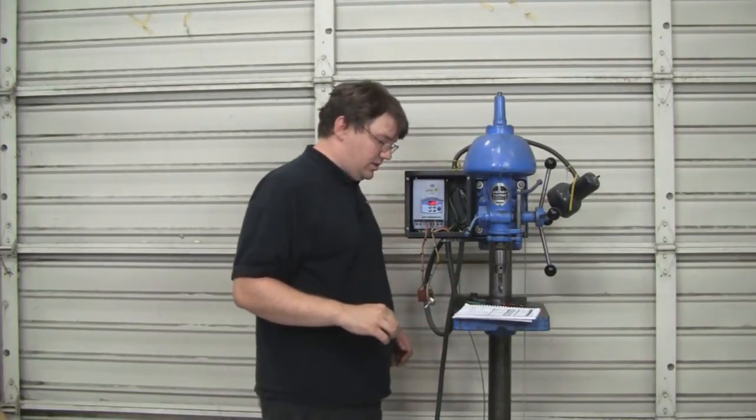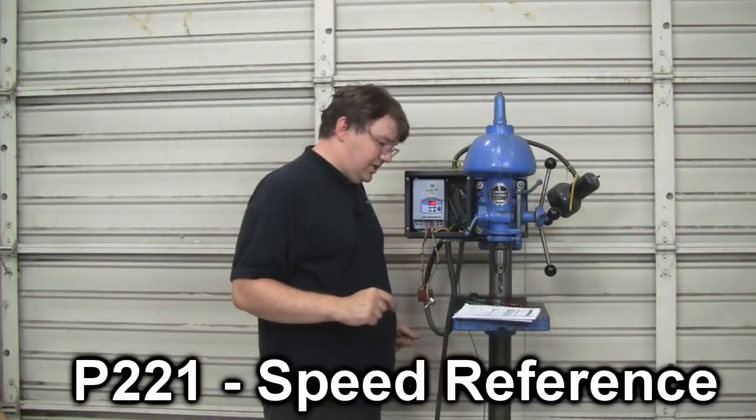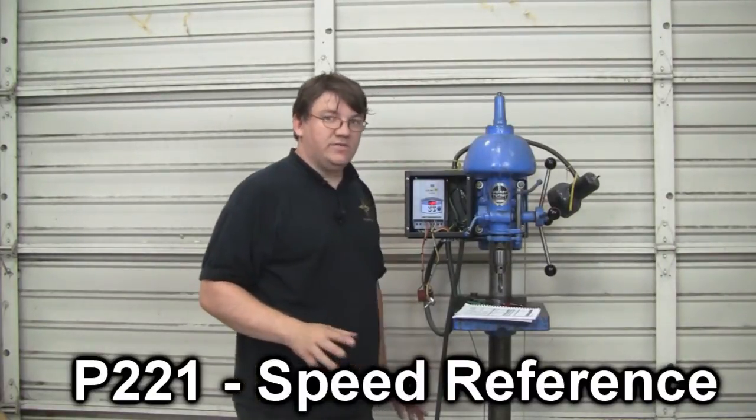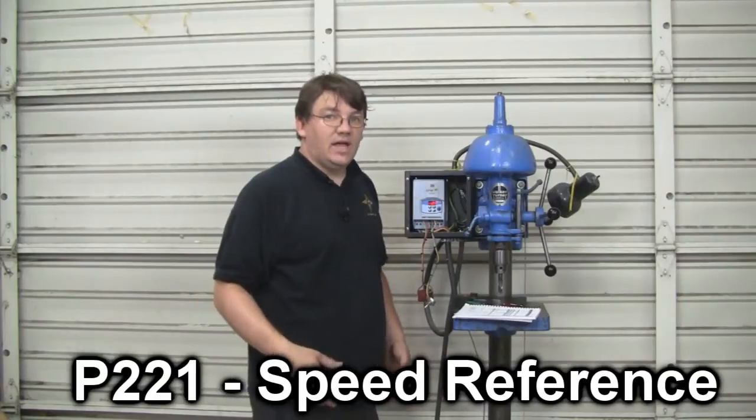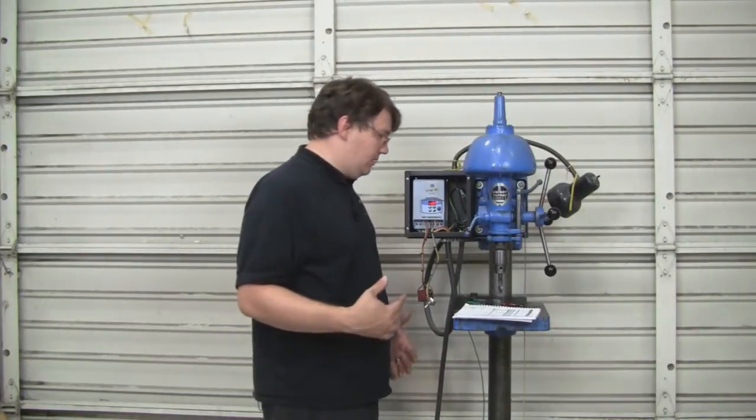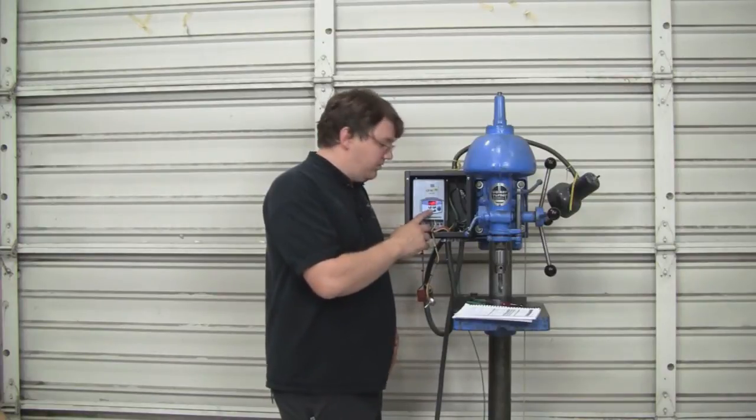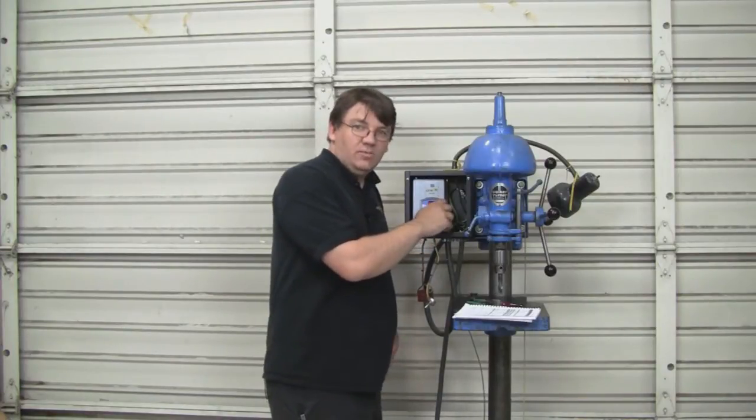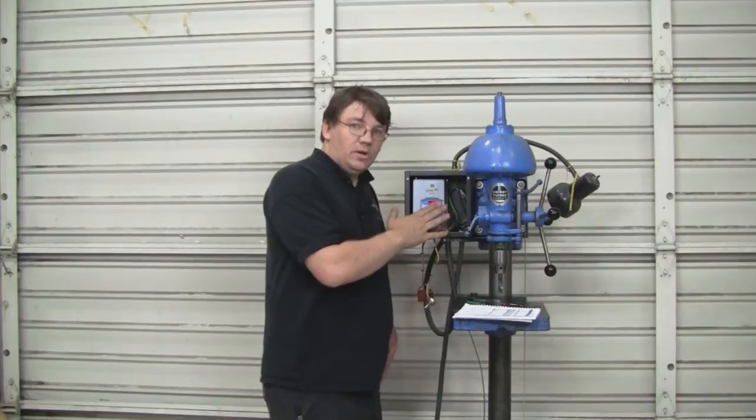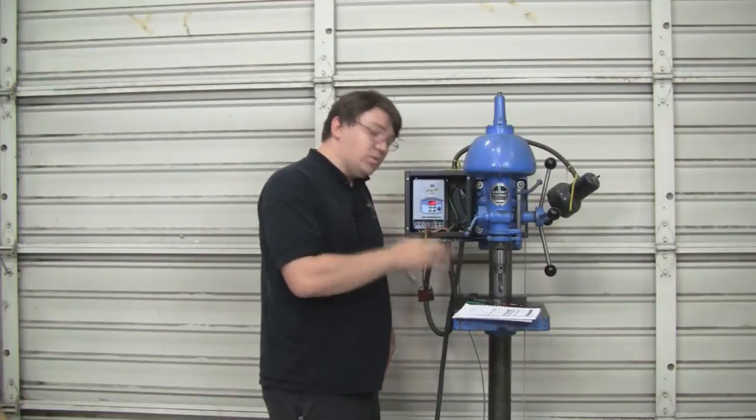The first one you're going to want to set, this is P221, which is your speed reference. This tells the VFD where it's getting how fast it should go. Normally that would be via the up-down buttons on the keypad, or if you had one with the built-in potentiometer, a lot of times it will be programmed to do that. But in this case, since we want it on the outside...